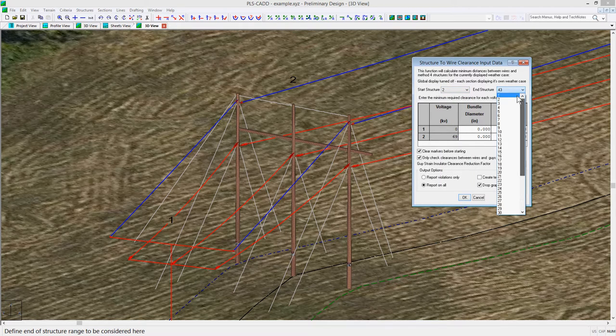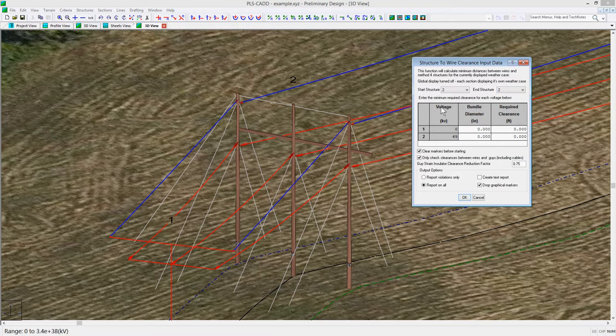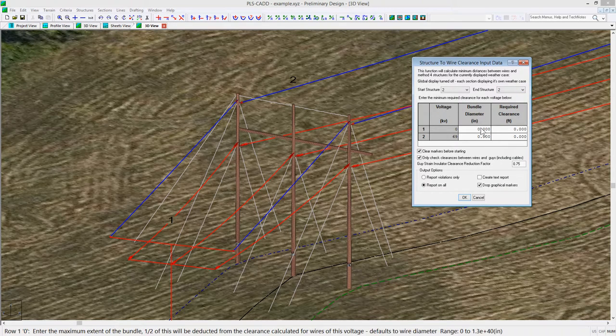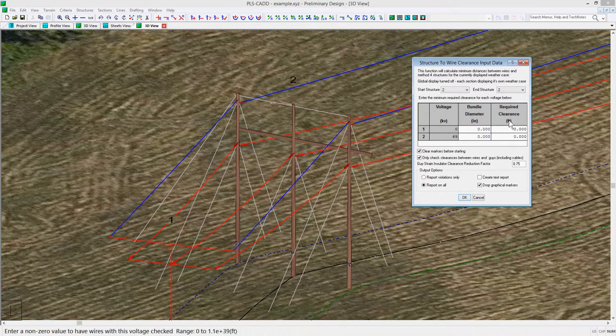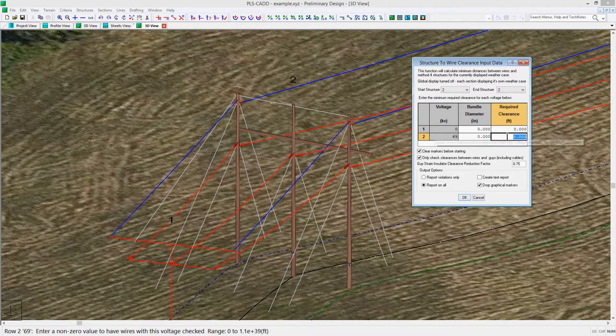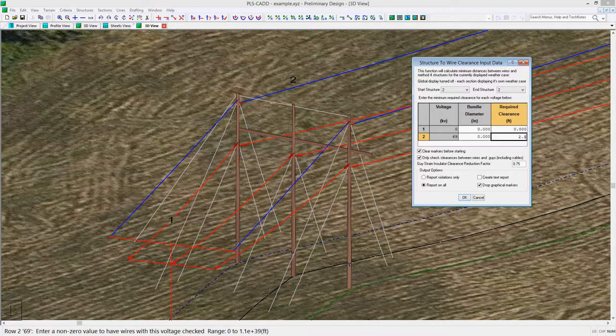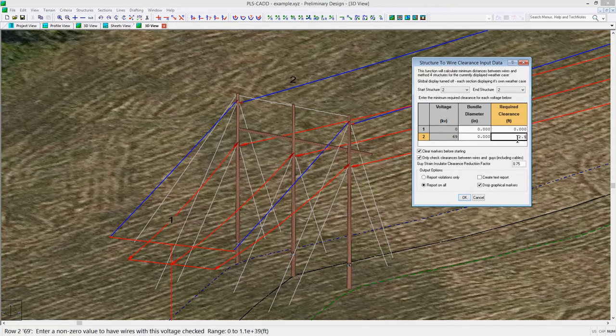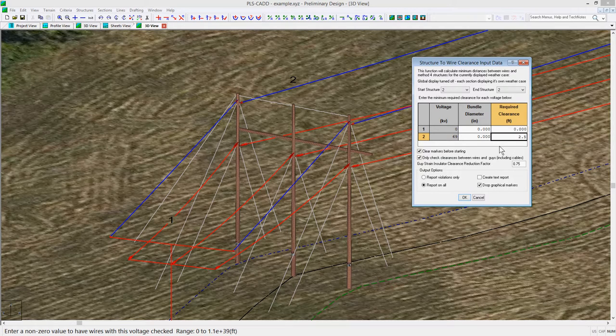In the next table, you have the voltage of all lines in the model, and you can enter a bundle diameter if needed, and the required clearance for each voltage. For this example, there is no bundle, and we'll set the required clearance of the 69 kV line to 2.5 feet.